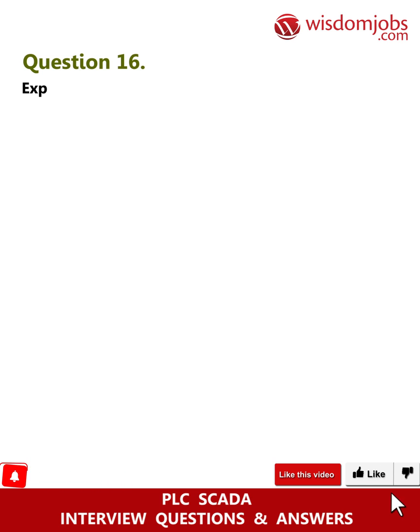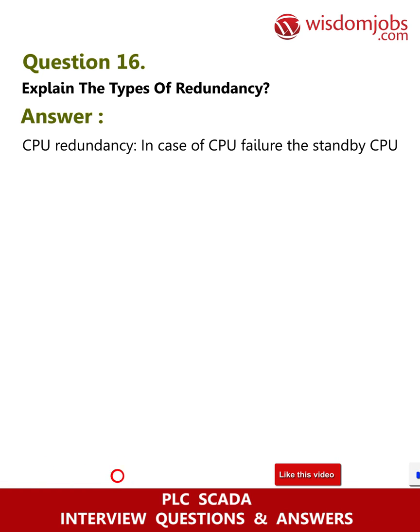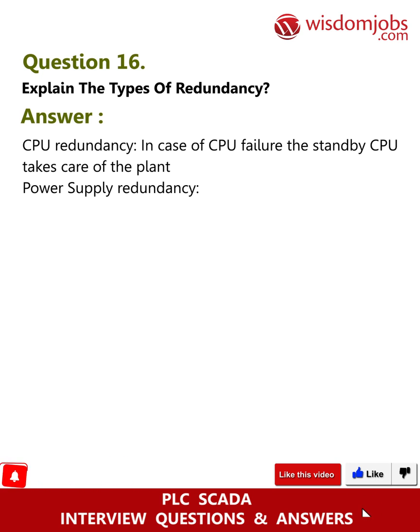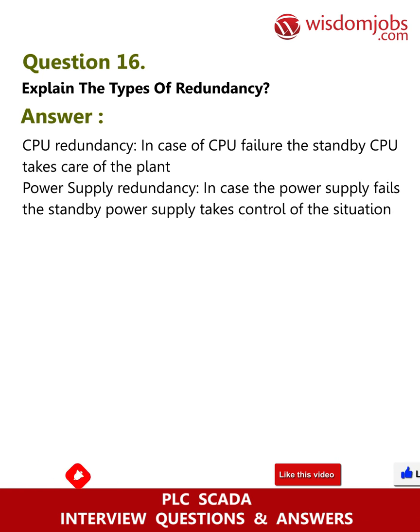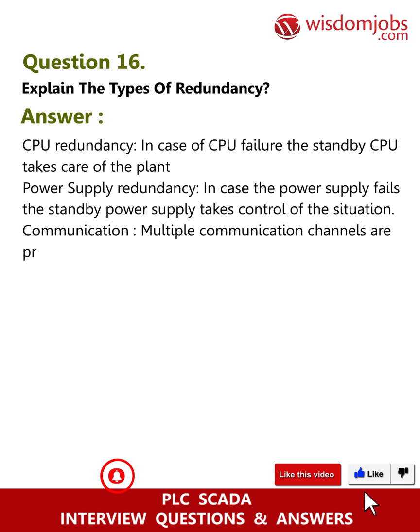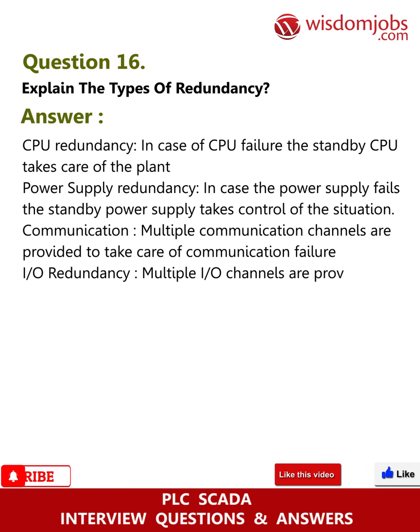Question 16: Explain the types of redundancy. Answer: CPU redundancy — in case of CPU failure, the standby CPU takes care of the plant. Power supply redundancy — in case the power supply fails, the standby power supply takes control of the situation. Communication — multiple communication channels are provided to take care of communication failure. I/O redundancy — multiple I/O channels are provided to take care of input or output failure.